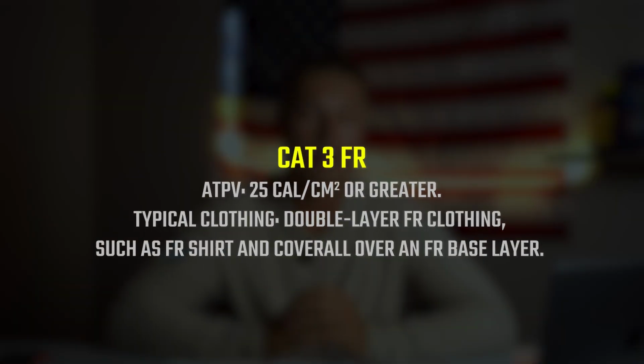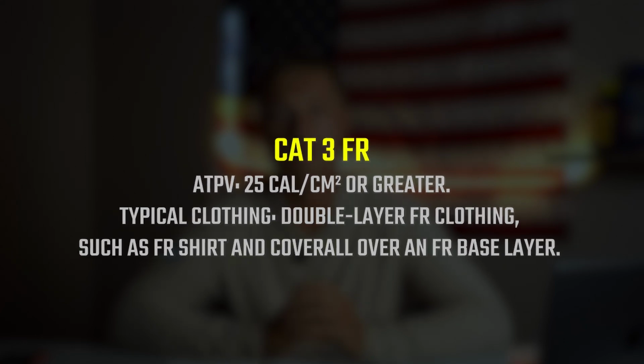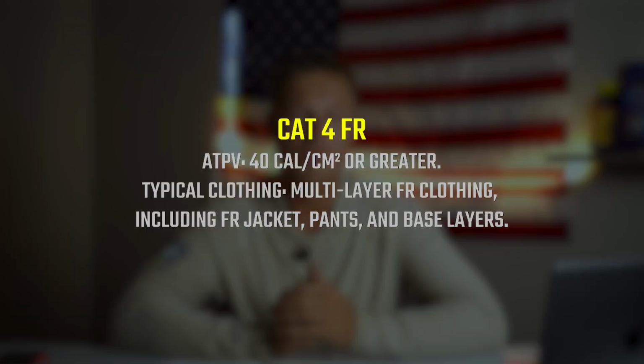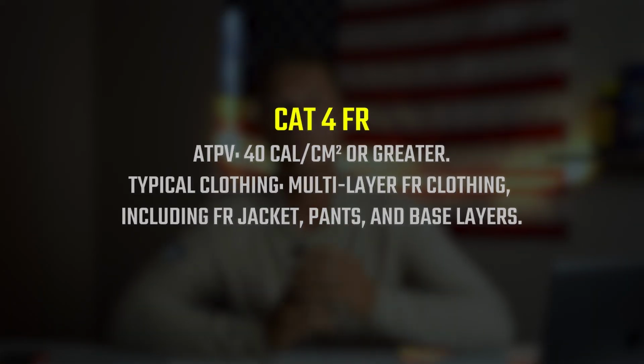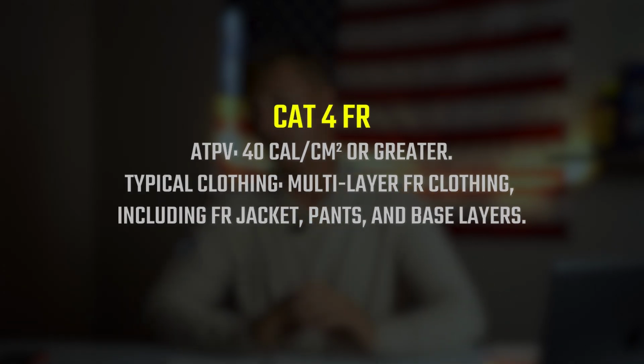Like I was saying, for us linemen working, we need to have a minimum of a Cat 2 as an outside layer for protection against arc flashes. Then you'll have a category 3, which usually has an ATPV rating of 25 calories per centimeter squared or greater, which is even better. Those are things like your sweatshirts or thicker pullover hoodies. Then the last is category 4, which usually has an ATPV rating of 40 calories per centimeter squared or greater. That's really things like a big pullover sweatshirt, a big jacket, or big overalls. Those are going to be category 3 or 4, which are just thicker fabrics.